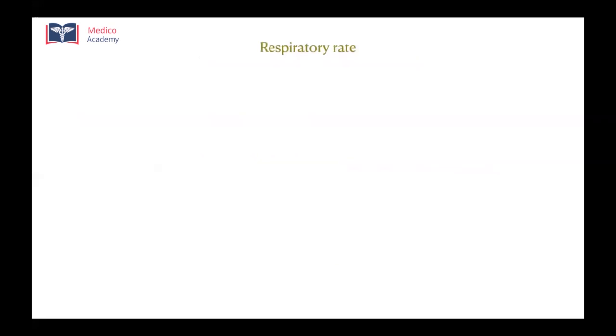So the next variable is respiratory rate. So if you need to achieve a minute ventilation of 5 to 10 liter per minute, you need to set a respiratory rate as well, right? So your basic principle should be to avoid acidosis as well as alkalosis. Try to maintain a normal pH of 7.35 to 7.45, and this can usually be achieved with a breath rate of 12 to 18 breaths per minute.